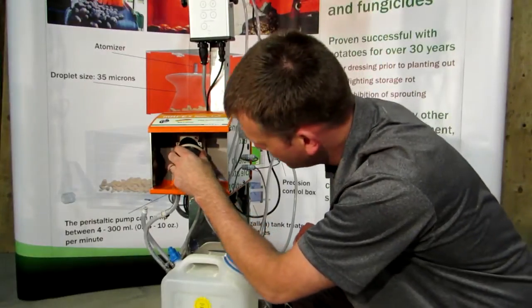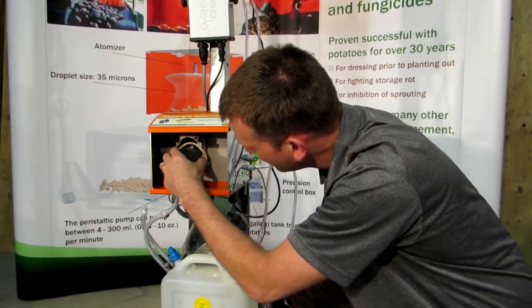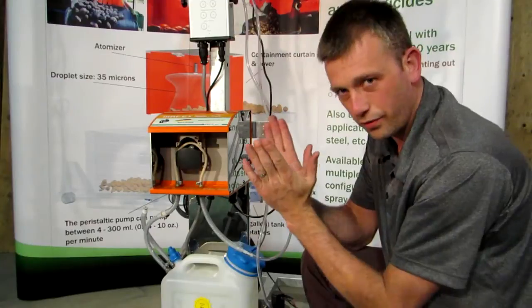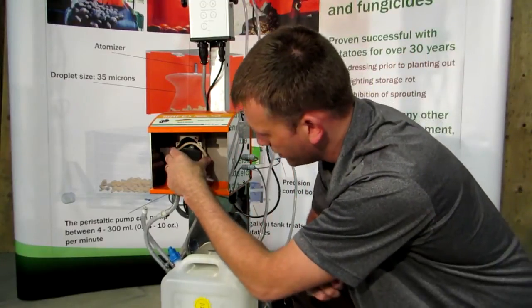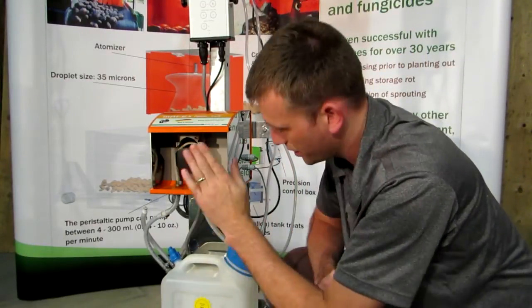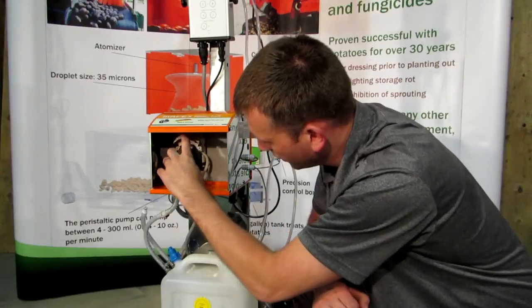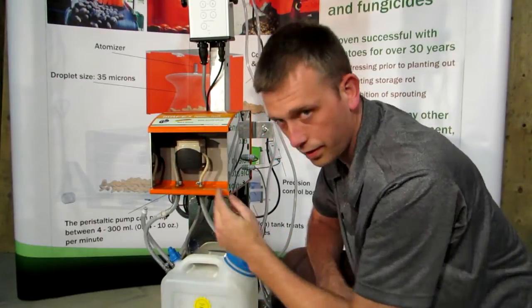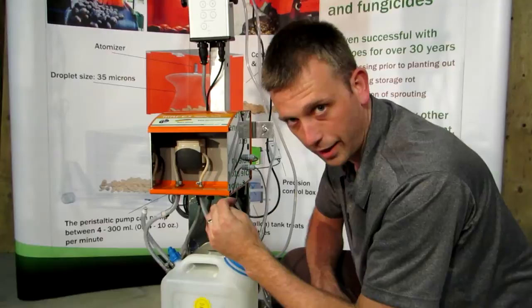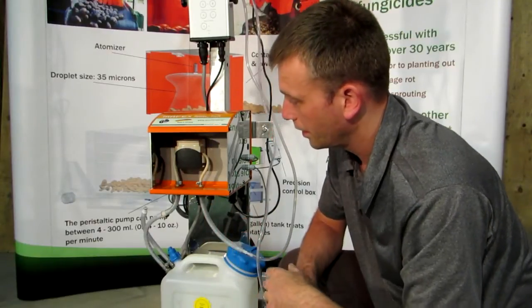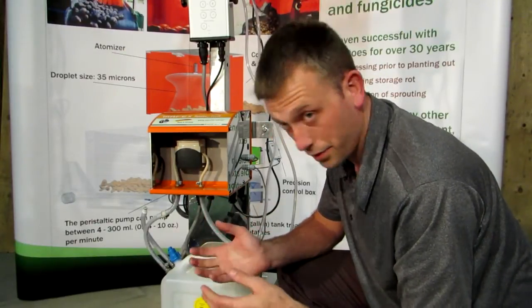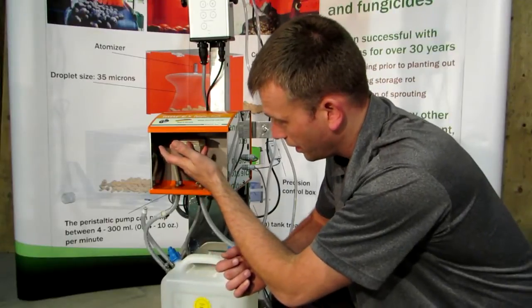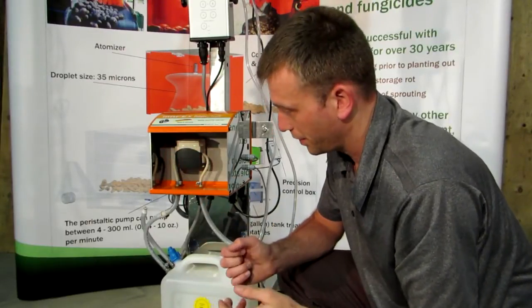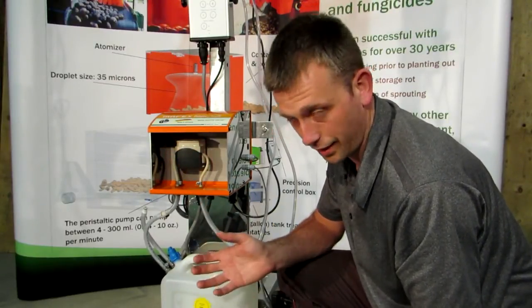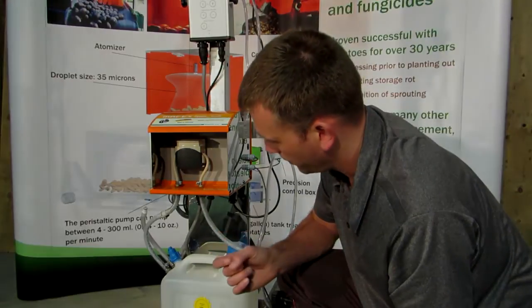And the hose sits on top of those rollers. There's 2 V's where the hose has to sit in. Please make sure that the hose is centered there, and then clamp down the top. If the top's not clamped down, it's not going to pump. Also, conversely, if you're not using the machine for a period of time, releasing the tension on the pump will greatly increase the lifespan of that hose as well.